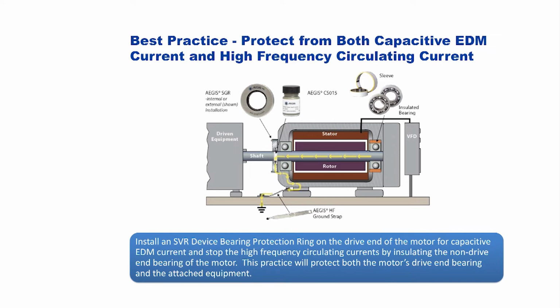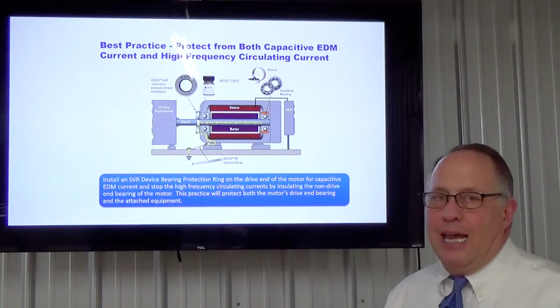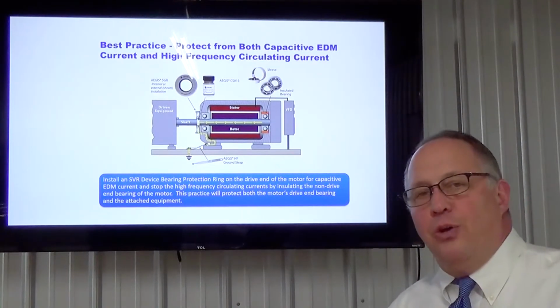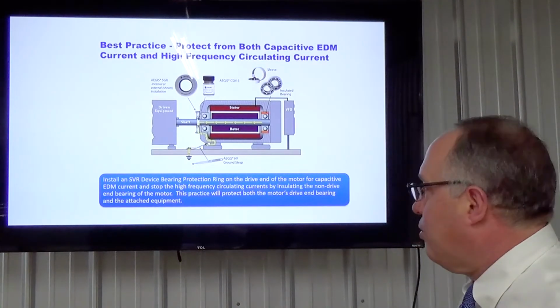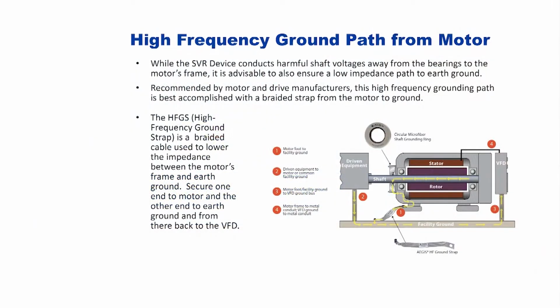In other words, using insulated bearings just on the non-drive end of the motor. This practice will protect both the motor drive end bearing and attached equipment. So you're looking at how do we get rid of it? This is a terrific way to do it. High frequency ground path from the motor.